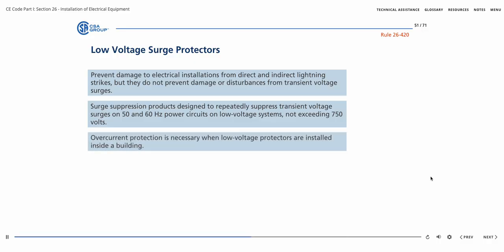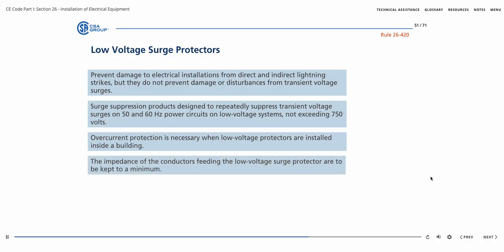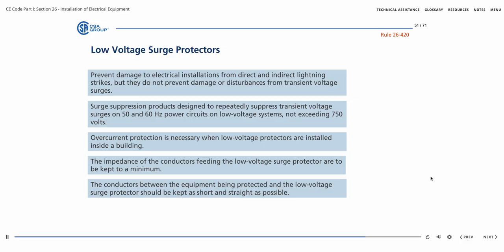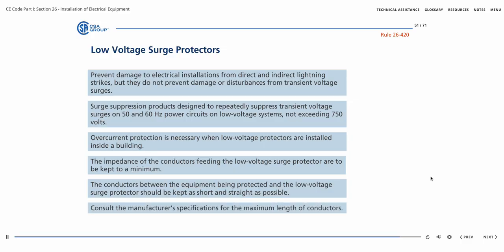To prevent a fire hazard inside a building due to damage to the low-voltage surge protector or the conductors feeding it, overcurrent protection is necessary when low-voltage protectors are installed inside a building. To enable low-voltage surge protectors to divert the damaging high-voltage spikes or transient voltage to ground, the impedance of the conductors feeding the low-voltage surge protector is to be kept to a minimum. The conductors between the equipment being protected and the low-voltage surge protector should be kept as short and as straight as possible. The manufacturer's specifications should be consulted for the maximum length of conductors.